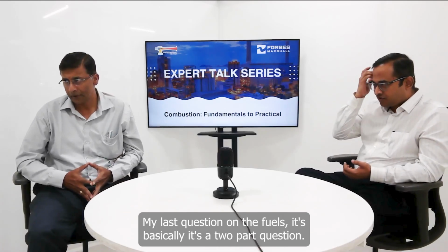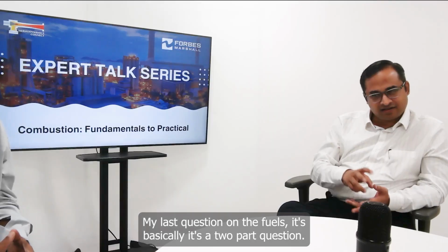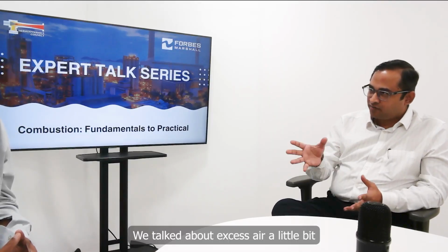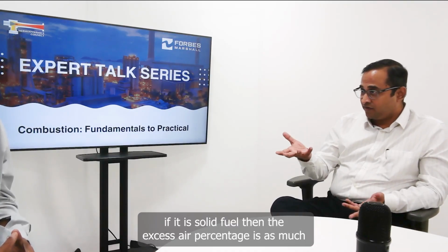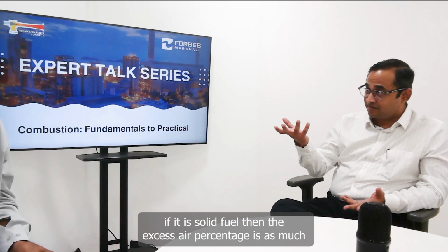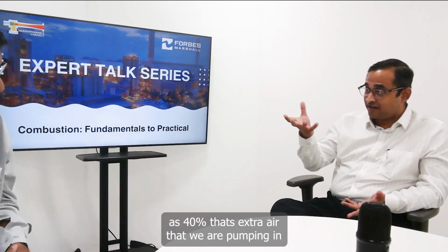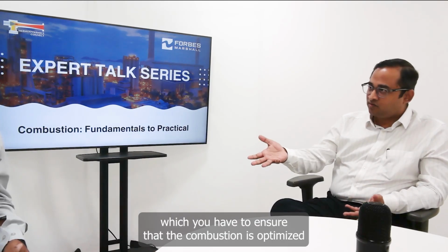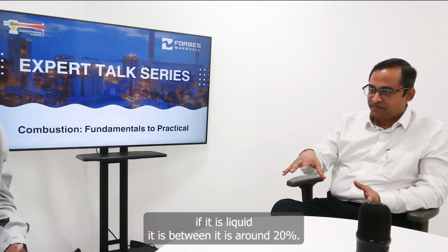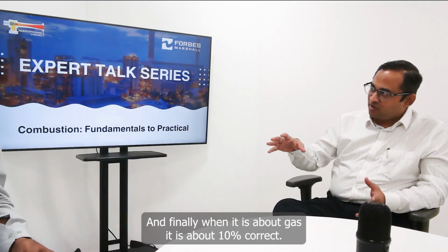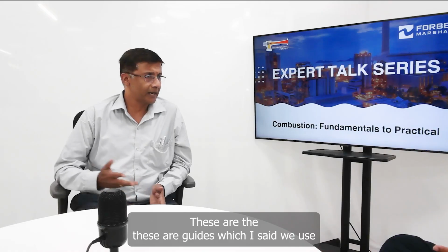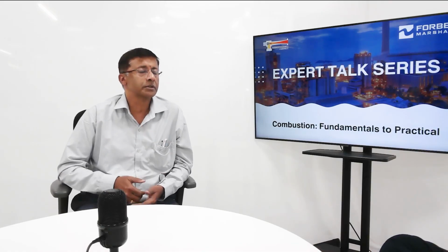My last question on the fuels, it's a two-part question. We talked about excess air, and you did give us some numbers. If it is solid fuel, then the excess air percentage is as much as 40%. That's extra air that you're pumping in, and you have to ensure that the combustion is complete. If it is liquid, it is around 20%. And finally, when it is gas, it is about 10%. These are guides which we use.